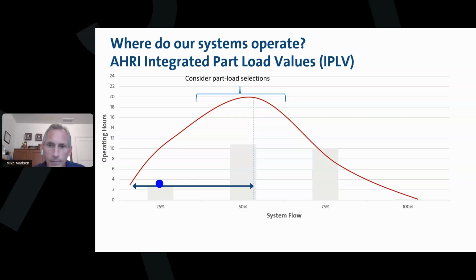And Mike, I just want to make sure I got this. So when we see a pump that's maybe like 87% efficient, that means that's when it's at 100% system flow, right? That's correct. 87. So really, it's a lot less most of the time. It can be. So it depends. You want to pick. So an old trick before our software was smart enough to do this selection, we would say in a variable load application, you pick your pump to the right of best efficiency point. So that way, as you slow the pump down, you cross back through best efficiency point and stay on the high part of the efficiency curve. Whereas if you just picked a pump to be very efficient at this full load condition, it may only go downhill from there. It just depends on the selection.